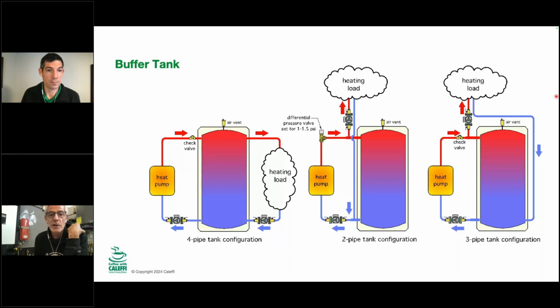The three pipe, did you talk about that one a little bit? Yeah, it takes it one step further. And what it does is on this three pipe, all the return water comes straight across the tank back to the heat pump. So you're going to get your lowest possible return temperature. This could be a boiler, a ModCon boiler, or a heat pump as we're showing in this, which will keep the efficiency of that device up, the cooler the water comes back to it. With the other one, you don't get direct back through the tank. So we're still engaging the tank up here on the top, but by coming through the bottom straight back, we're going to get the lowest return.